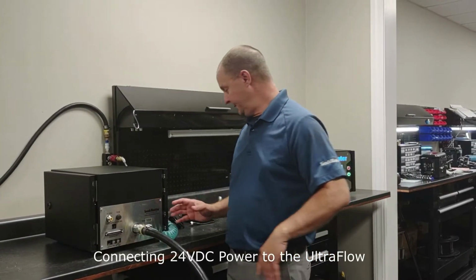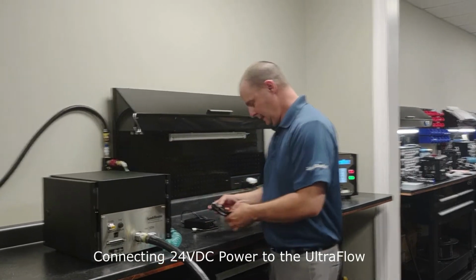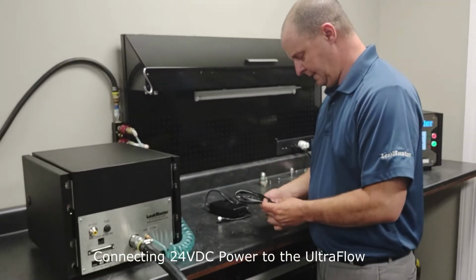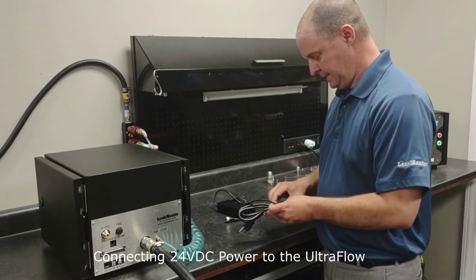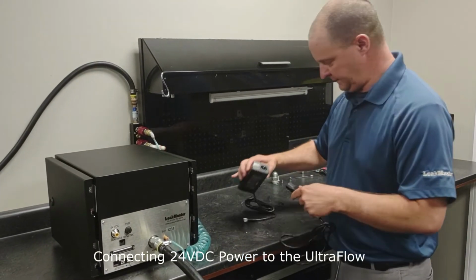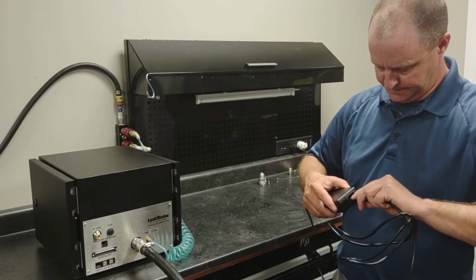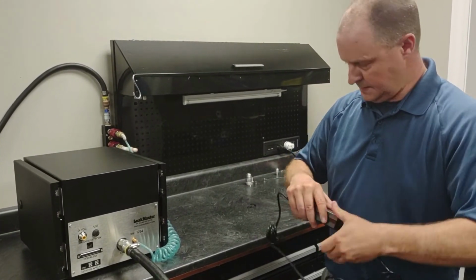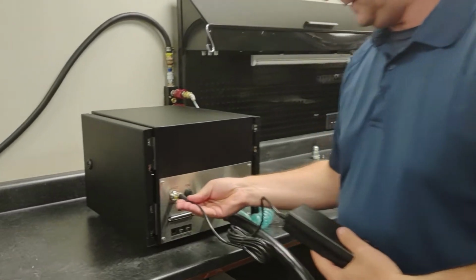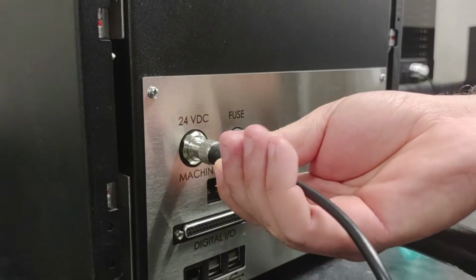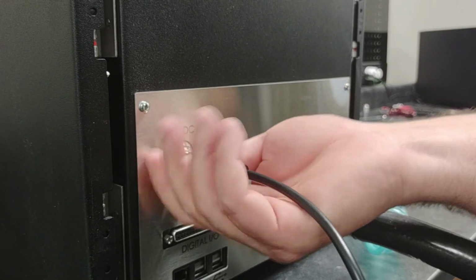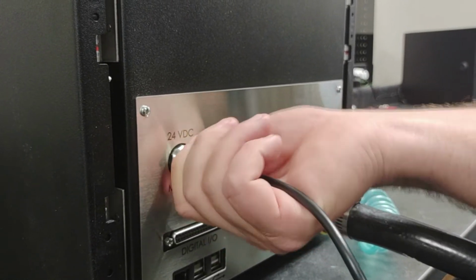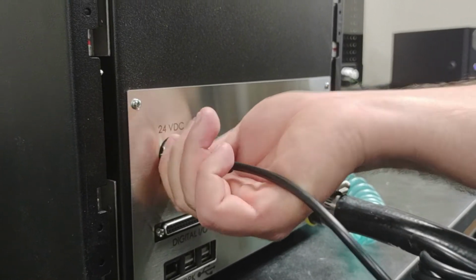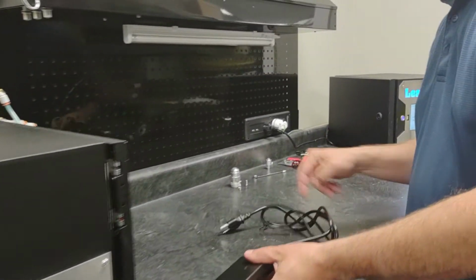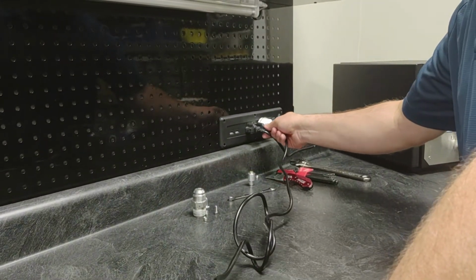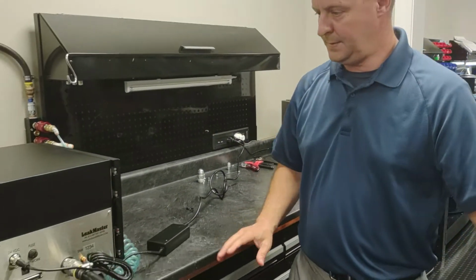Now that we've got the unit plumbed up, it's time to apply power to it. There's two options for this. If you don't have a 24-volt power supply, you would be buying the option, the 120-volt AC adapter. You're going to plug that directly into this 24 volt DC power inlet. This is an M12 Euro style connector. Thread that guy all the way in. Plug the other end to a 120 volt AC source, and your power is applied.